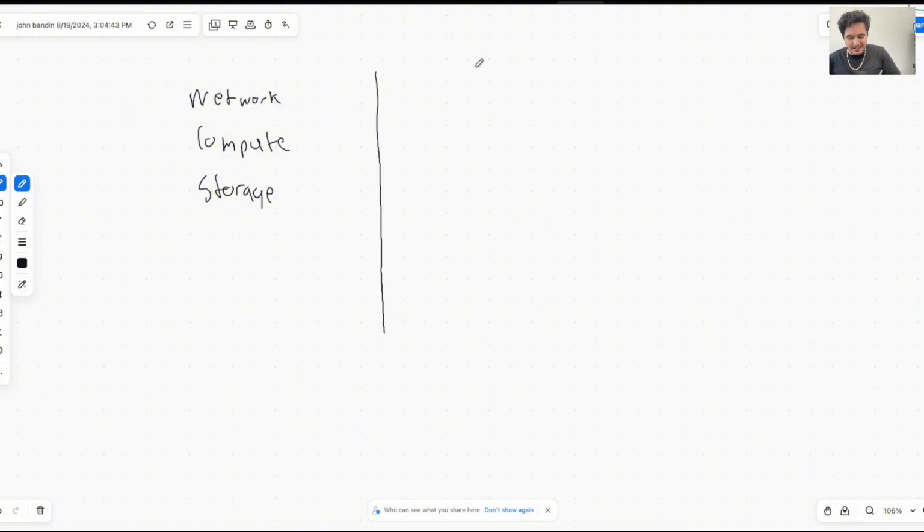So if I were to draw a data center rack here, maybe at the bottom we'd have power. That's something that's also basic in IT and technology in general. We need power. So at the bottom here would maybe be a power distribution unit, maybe up top a UPS. And if this was an on-prem data center, this would maybe be a generator. We'd have multiple lines coming in from the grid, zoned correctly, and a generator as a backup doing ATS, automatic transfer switching. Then each rack would probably have its own UPS rated for whatever wattage, to last 30 minutes, an hour, or 2 hours, depending on how much we care about power redundancy. So down here we'd have a UPS, an uninterruptible power supply. It's a big battery backup, okay?